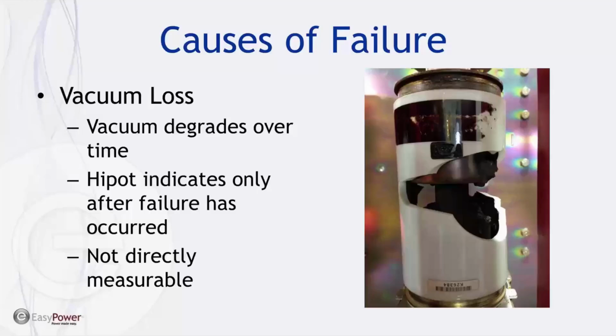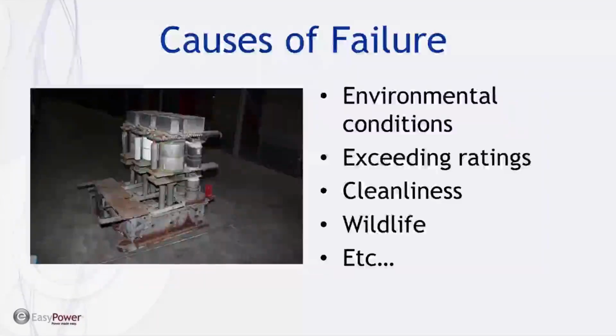One of the problems with vacuum loss is that the accepted test for determining vacuum loss can't tell you exactly how close to failure you are. It can only tell you right now, at this moment, failure has or has not occurred. And so up to this point, the vacuum has been a mystery, and there have been lots of attempts at determining the vacuum. Some people try to trend DC leakage currents, and there are other methods that people have tried, but they're not reliable, and there's not been a real consensus on it. And of course, there are other causes of failure.